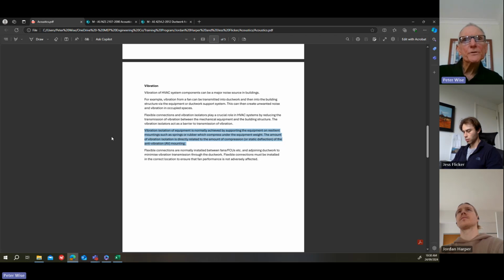Vibration isolation of equipment is normally achieved by supporting the equipment on resilient mounting such as springs or rubber, which compress under the equipment weight. So you would have seen this. For fans, you can use either rubber mounts or spring mounts. Pumps are normally mounted on springs, quite often with an inertia base to absorb the force when a pump starts. There's a centrifugal force, so the mass of the inertia base helps to dampen some of that, and then the whole thing is mounted on springs.